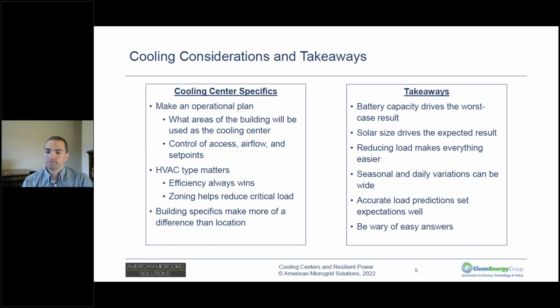So having an operational plan for how you'll actually implement the load shedding you want is really important. Also specific to cooling centers is that the HVAC type really matters. Let's take two opposite ends of the spectrum as examples. In the Southeast case study, there's one very large chiller outside that provides cool water to the entire building, and the air handlers blow over those cold coils. That's one very large component servicing the whole building. It can't run below a certain capacity, so when it fires up, it has a very large starting surge. That's a problem we need to handle in the design of the microgrid. And it will draw a decent amount of power whenever it's operating.